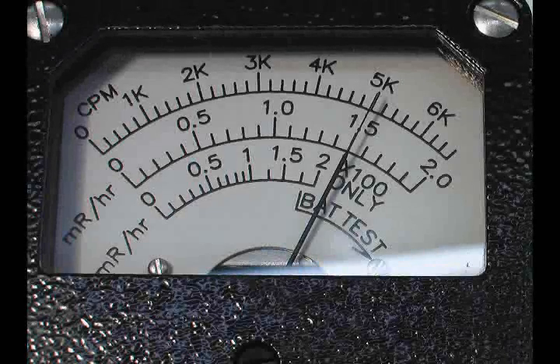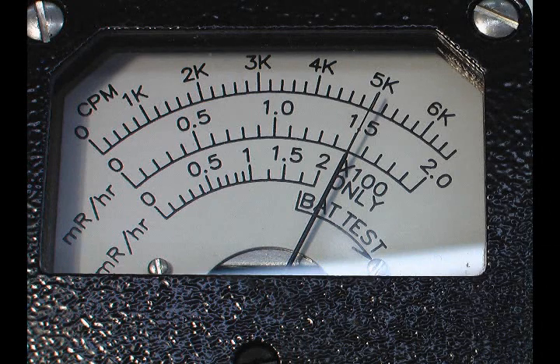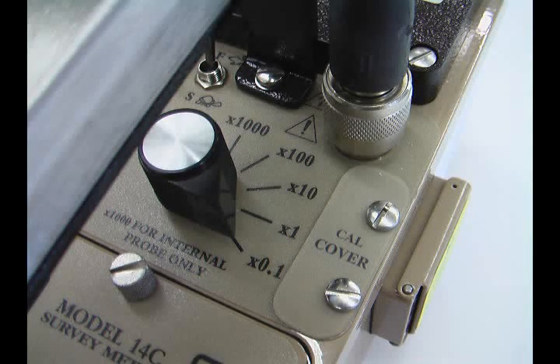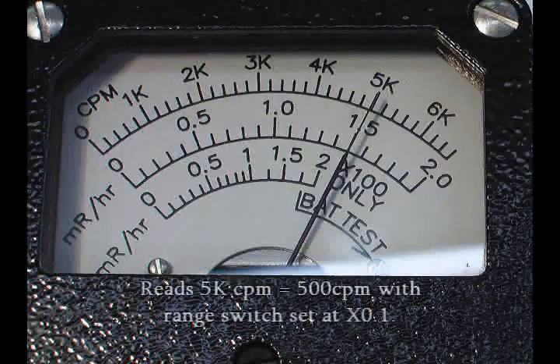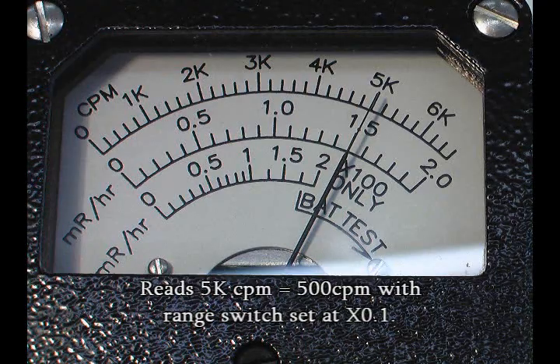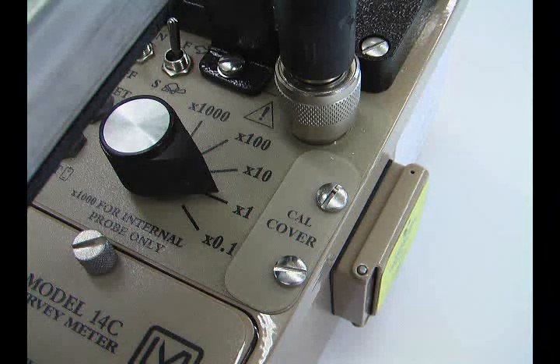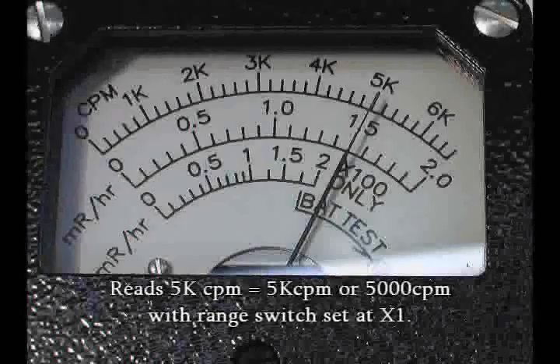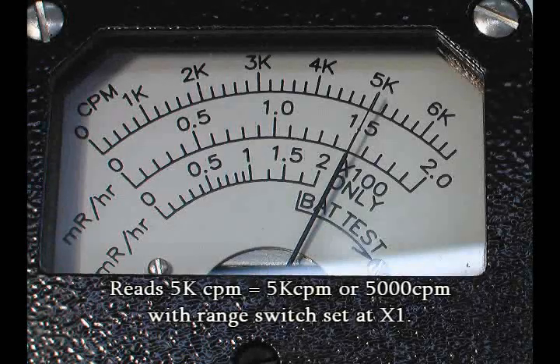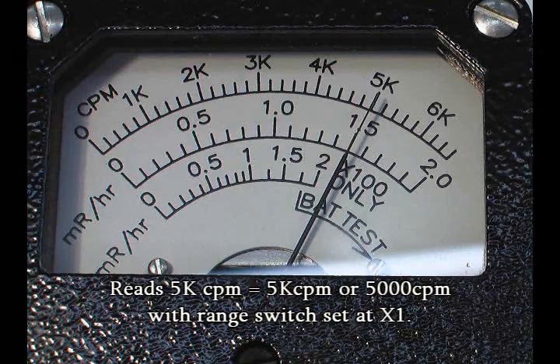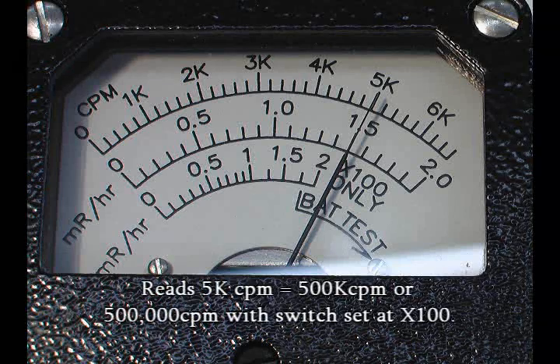In this example, reading the top CPM scale, the meter needle is on the 5K tick mark, and the range selector switch is on the times 0.1 setting. The reading will be 5K CPM or 500 CPM. Changing the range selector switch to the times 1 setting will change the reading to 5K CPM or 5,000 CPM. Changing to the times 100 setting, the reading will be 500K CPM or 500,000 CPM.